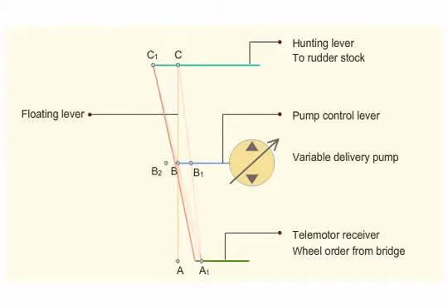When the steering wheel is moved to midships, the telemotor control will move the floating lever back to A, pulling the pump control rod to B2. The pump will discharge in the opposite direction, supplying pressurized oil to the other set of cylinders. This will turn the rudder in the opposite direction.